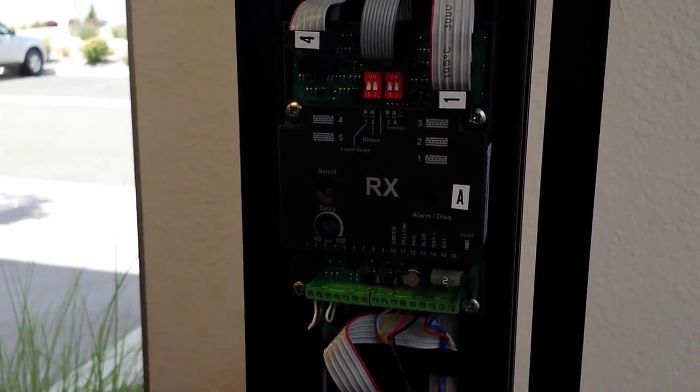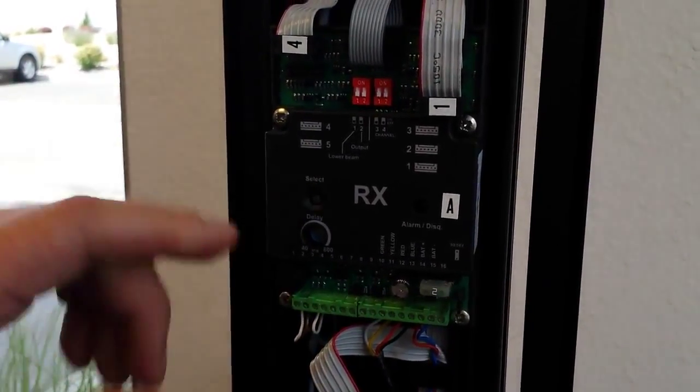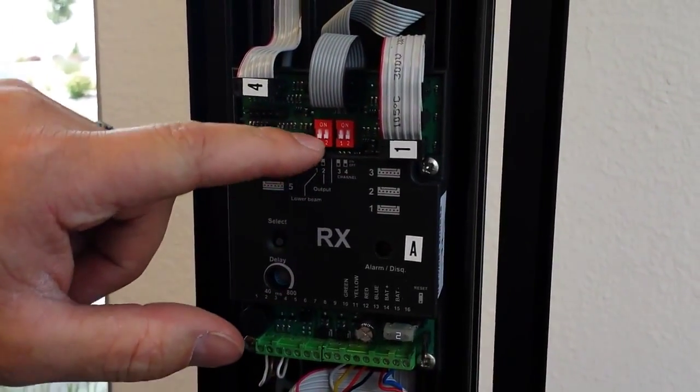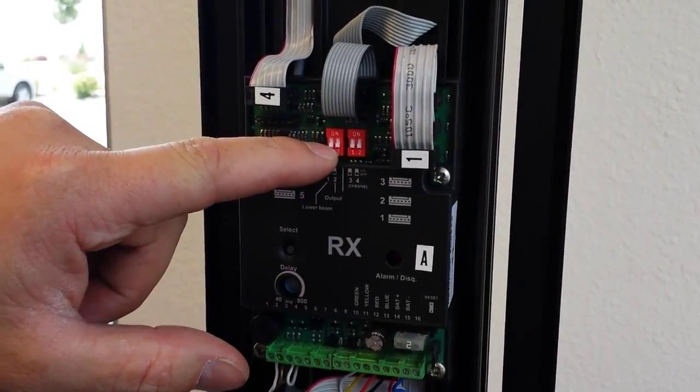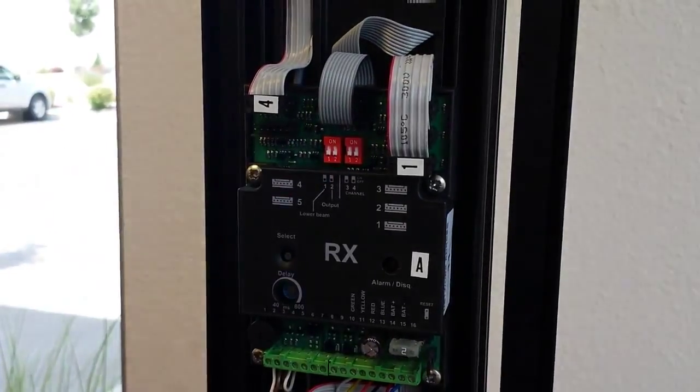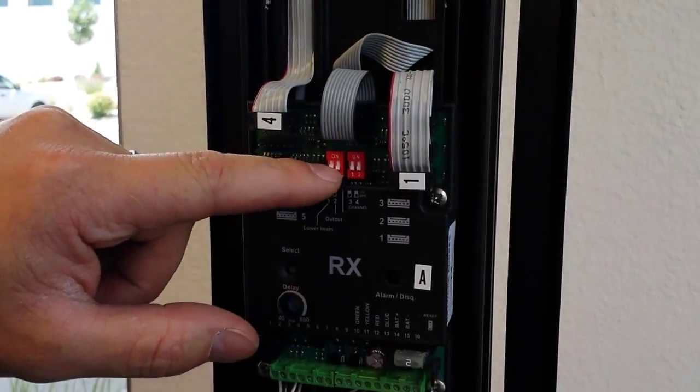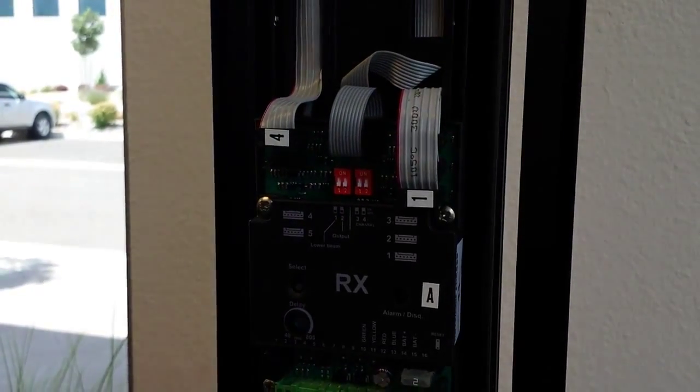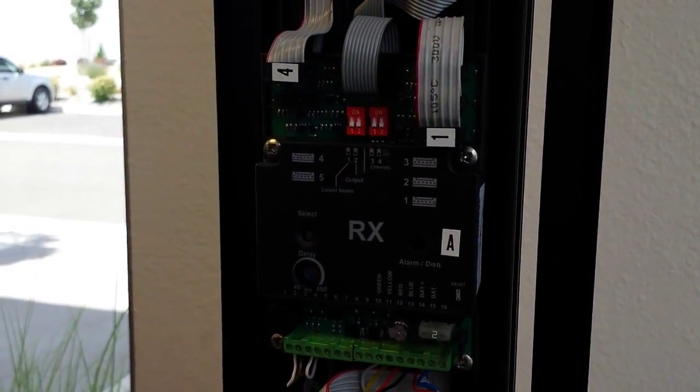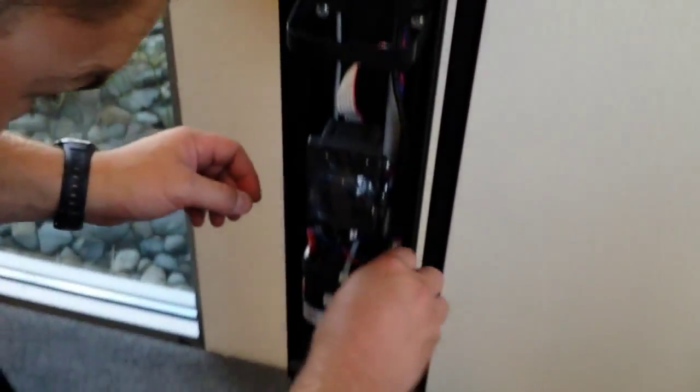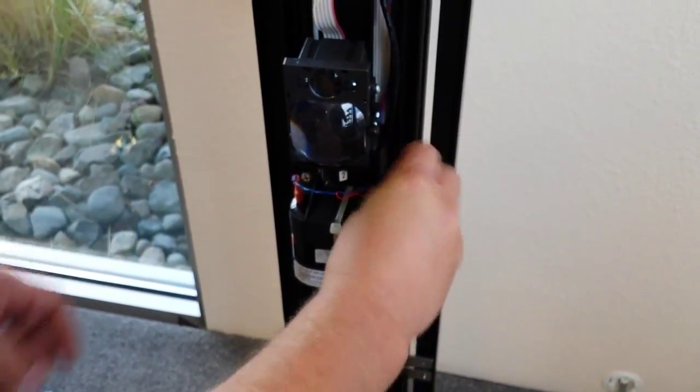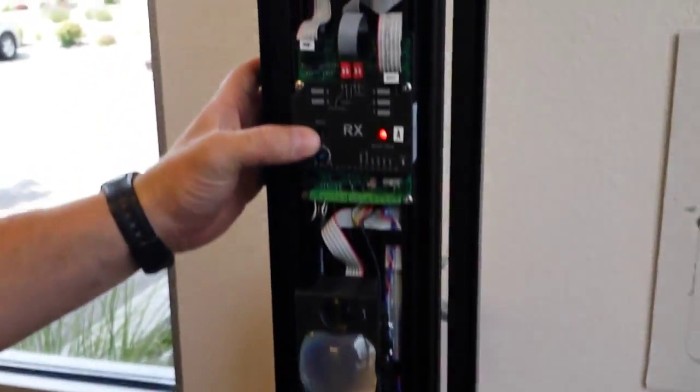This is our RX column. It has a channel selection just like the other side. And it has a switch right here for mono detection on the bottom beam. Switch these down in order to have mono detection on the bottom beam. Up turns off the mono detection on the bottom beam. So we're going to plug in this battery and then we're going to put this into alignment mode.